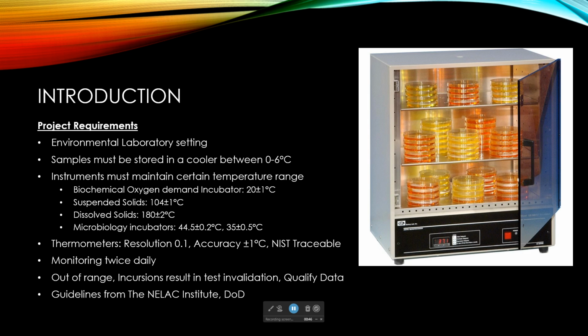For this project, I'm using the environmental lab setting where samples must be stored in a cooler between 0 to 6 degrees centigrade. There are also many instruments used in various tests that have to be at certain temperatures, like BODs, which have to be 20 plus or minus 1 degree centigrade, and various suspended solids and dissolved solids, used in wastewater and surface water analysis.